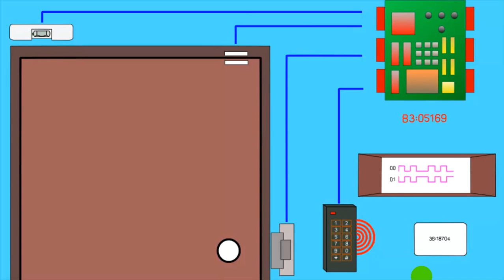How does it know what the string of zeros and ones mean? It uses a decryption template to translate the binary string into a card number. If the decryption matches the encryption on the card, it will read the correct card number and give access. If it's the wrong decryption, it will send an access denied message and not unlock the door. How does the controller know which user should have access or not? Everything is programmed from the Entrapass software on a computer.